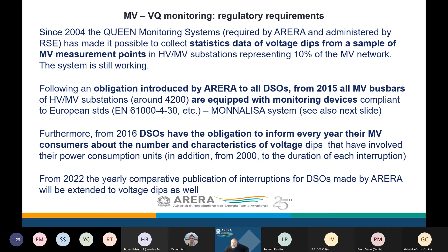Just to give you an idea, these are the results we can obtain from the MONNALISA monitoring system, which is somehow the evolution of the first QUEEN system, that now covers the whole medium voltage network. You can find here the average number of voltage dips per monitoring point, both looking only at medium voltage grid origin, or including also the high voltage grid origin.